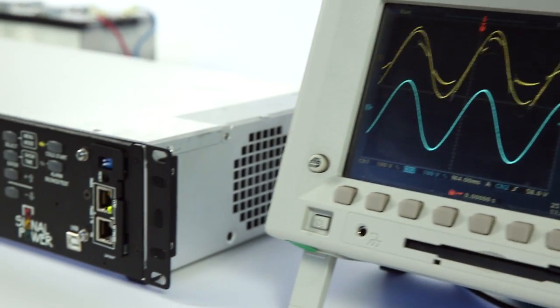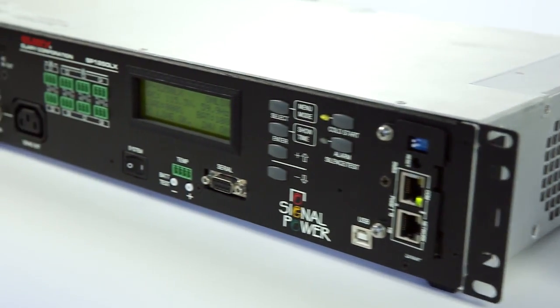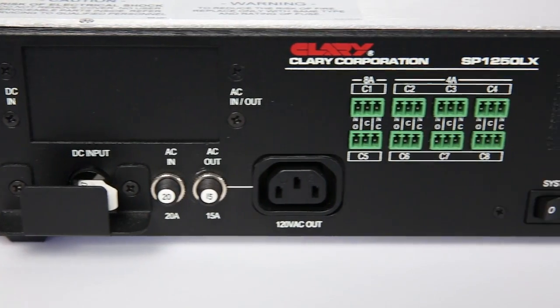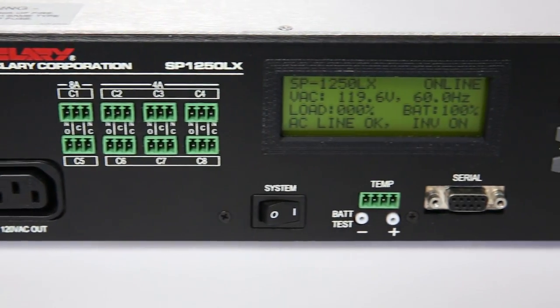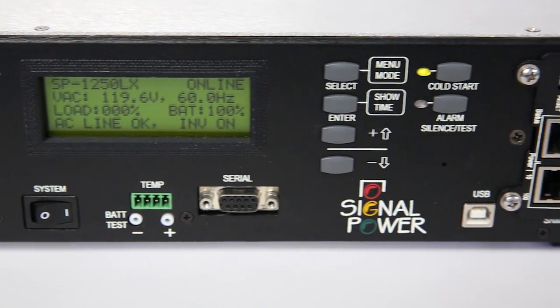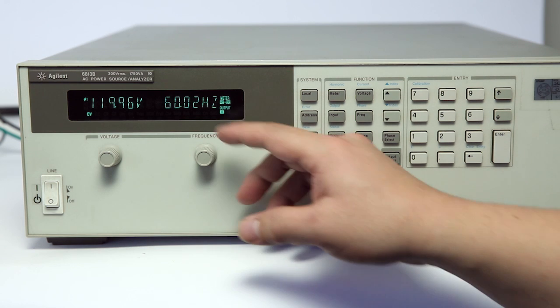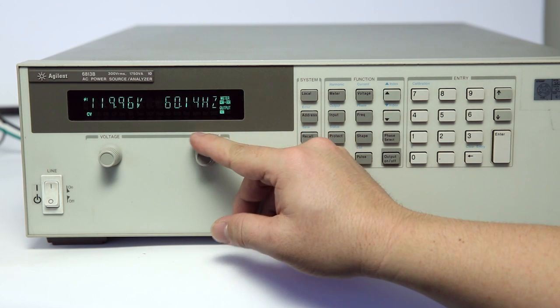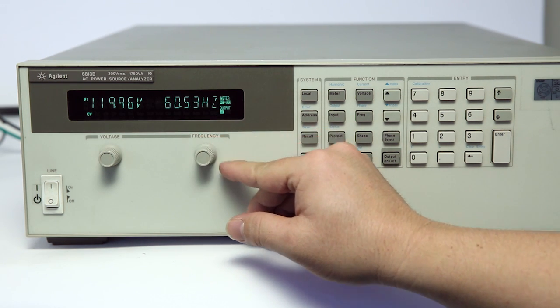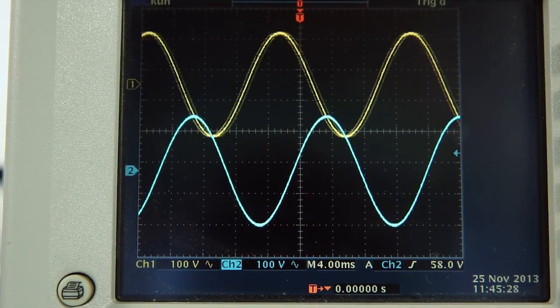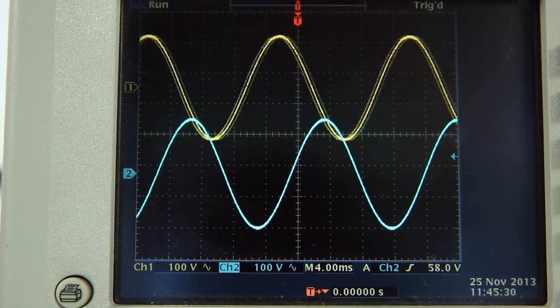Clary's UPS can operate on a dirty power supply such as a generator and alternative power sources that do not run the typical 60 Hz. Instead, these power sources can fluctuate consistently to between 58 and 65 Hz. To simulate this, the generator is going to be taken out of frequency and the line sync is then going to be disabled. The UPS is going to generate a nice clean 60 cycle from its free run operations.